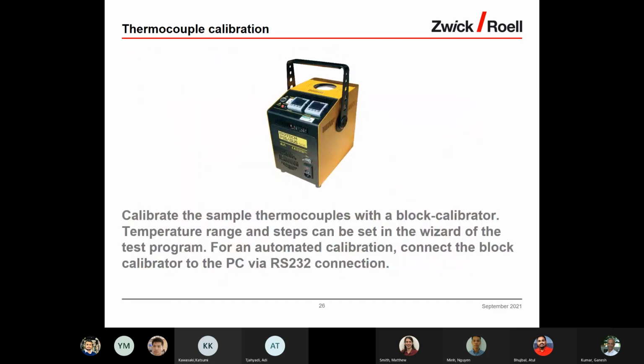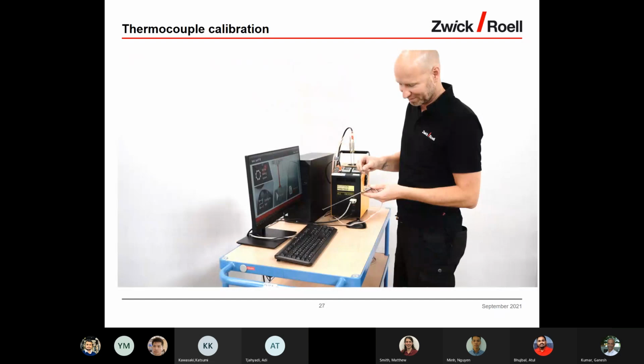The next page is to calibrate the sample thermocouple with a block calibrator. Temperature range and steps can be set in the wizard of the test program. For an automated calibration, connect the block calibrator to the PC via RS232 connection. Here's also a small movie.